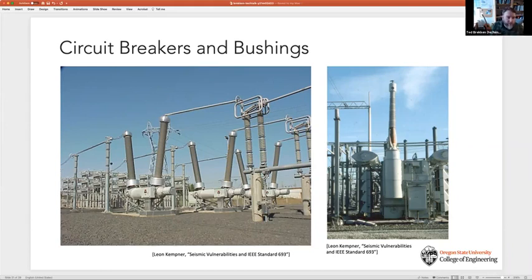Another thing being done, you can see where my cursor is pointing, there's a flexible connection from the rigid bus to the top of the bushing. In many substations these flexible connections are being retrofitted with more flex. That way, in the case of shaking, since you have two rigid structures that would otherwise oscillate at their own harmonic modes and pull on each other in a detrimental way, more flex allows each item to be more harmonically isolated from the other. So that's another thing being done.